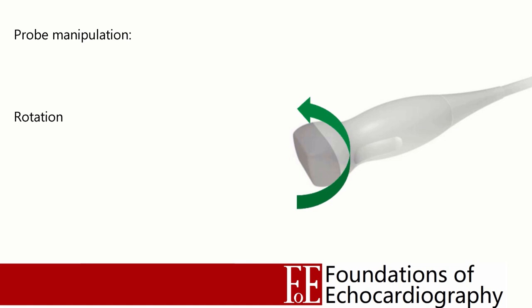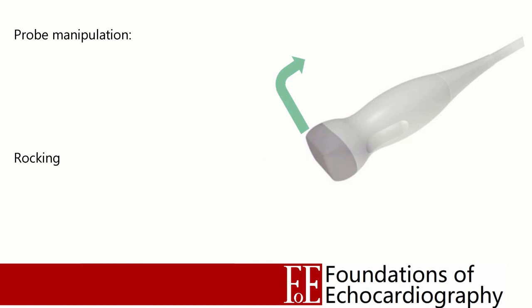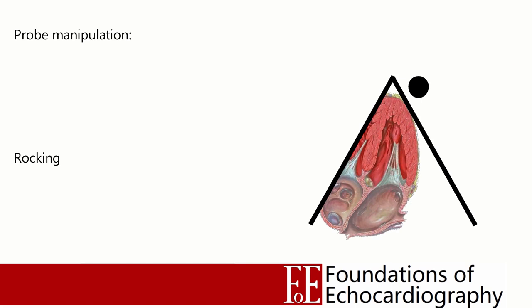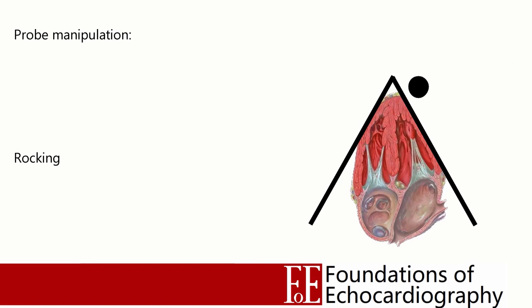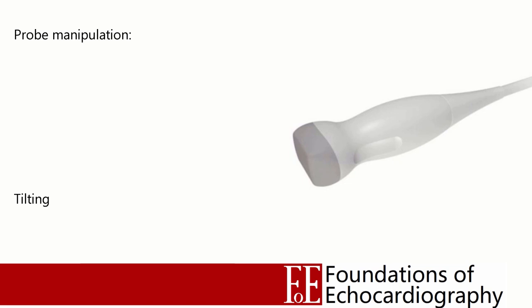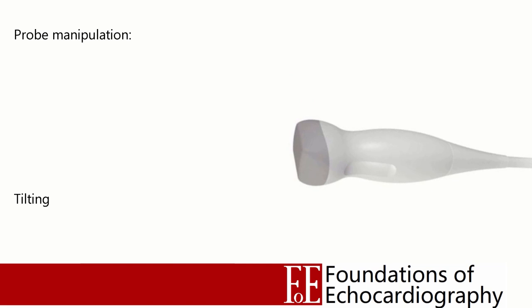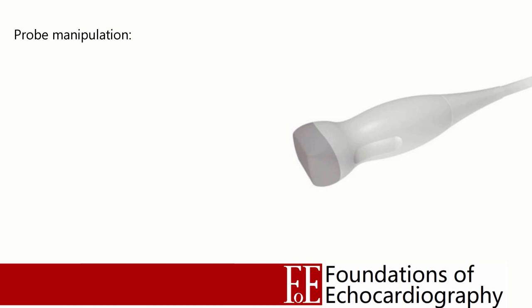Secondly we have rotation. Rotation is around the central axis of the probe and will either be clockwise or anti-clockwise. Third we have rocking. Rocking is parallel to the orientation marker and will cause the image within the sector to swing — for example, this is the motion required to centralise the septum in the apical four chamber view. The final probe manipulation is tilting. This is a movement of the probe perpendicular to the orientation marker and allows you to see in different planes.